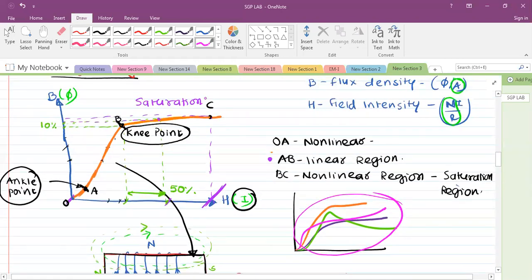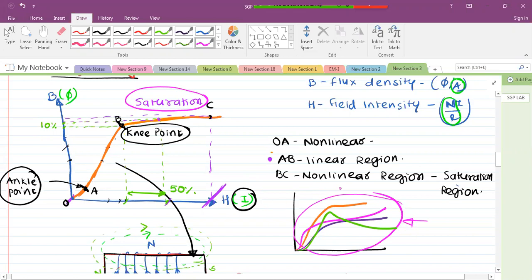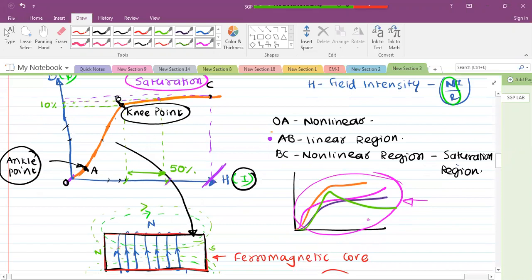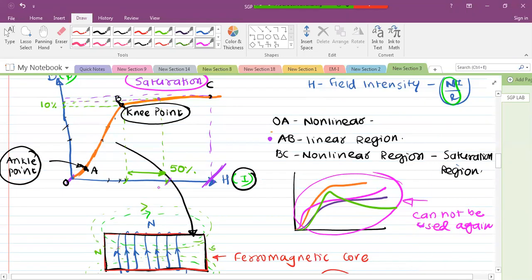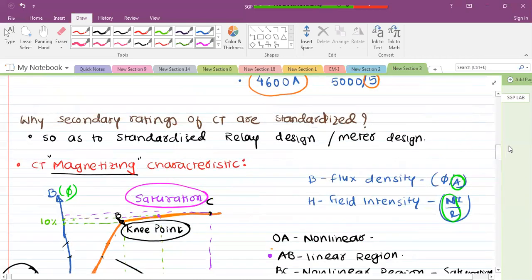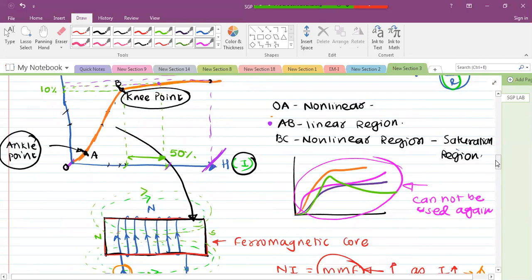Understand what is the meaning of saturation? Why we should not go into the deep saturation region? Because the core will lose its property of establishing the magnetic field. Every time you magnetize the core, it may behave differently, and that is why it cannot be used again. We have to replace the core if this happens. Suppose it is a 100/1 CT and it is saturated deep into the saturation region. Next time when you pass 100 ampere current, it may develop 1.2 ampere instead of 1. Next time it may develop 0.8 ampere, 0.85 ampere, 0.9 ampere, anything can happen, even 0.5 ampere. So it will not follow the standard ratio of 100/1 if the CT is saturated.